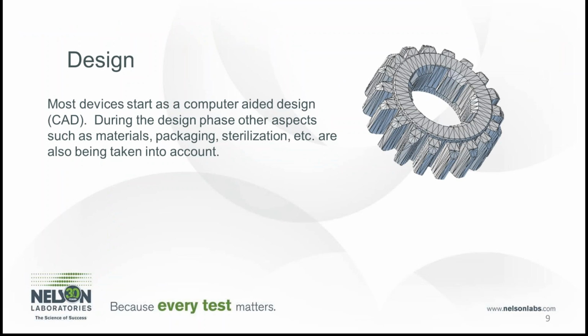Most devices and ideas start with a computer program, usually a CAD design, where you start looking at the overall shapes, the sizes, functionalities, placement of buttons, knobs, levers, wheels, etc. But you also start looking at the other aspects that accompany the device, such as what materials the device will be made of, the packaging, not only in the type of packaging, but dimensions and materials, sterilization, the type, EO, radiation, steam, E-beam, etc. All of these things need to be taken into account early on in the phase, especially with medical devices.